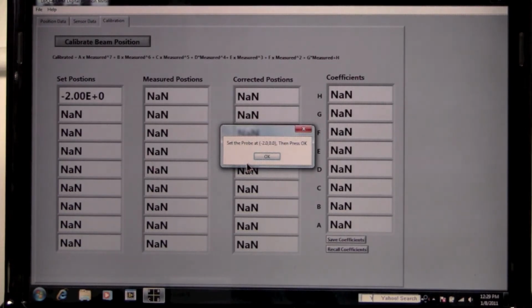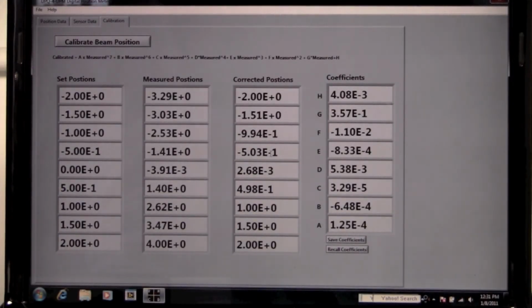Using the stage, move the quad detector in the x-axis only to the minus 2 millimeter position and hit the OK button. The instrument will measure and record the X position. Next, move the detector to the minus 1.5 millimeter position and hit the OK again. The process continues until the detector has moved to all 9 spots. After the last measurement is made, the data is fit to a multi-order polynomial. Correction factors are determined and applied to the raw XY data. And almost magically, the quad probe can now measure position accurately.